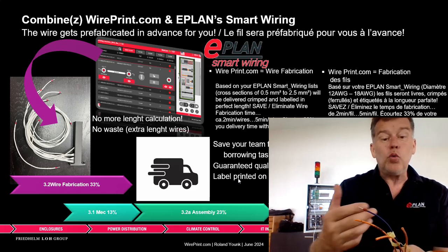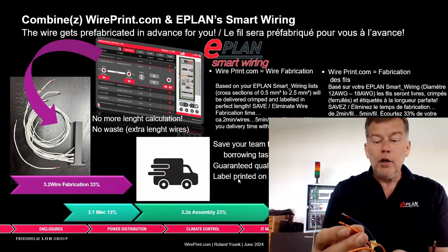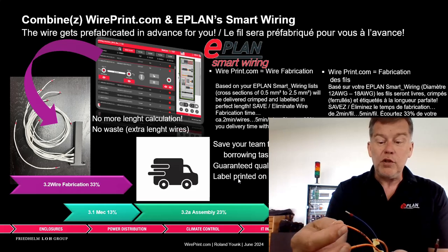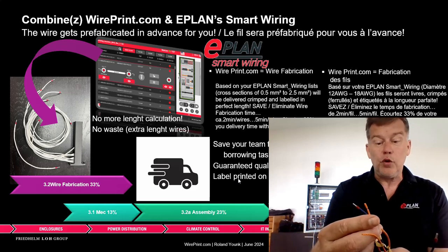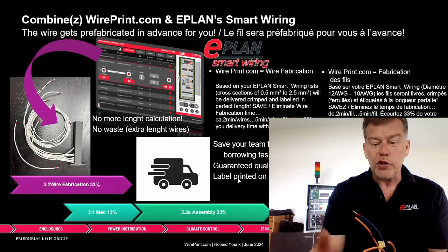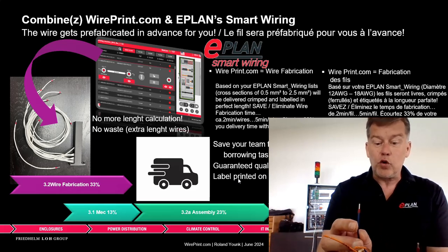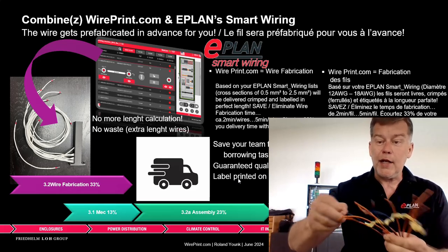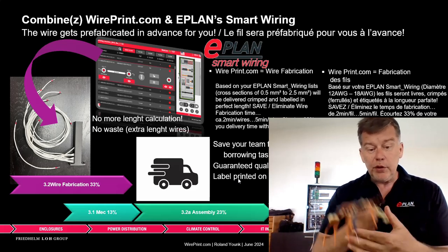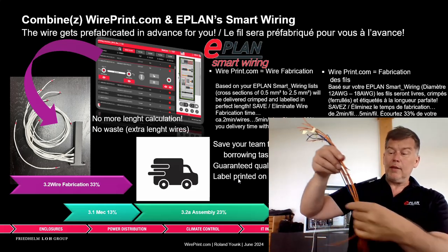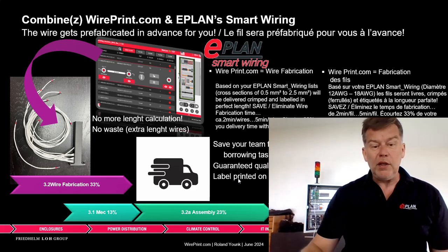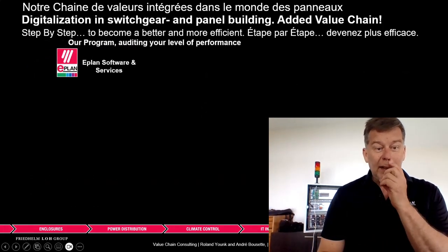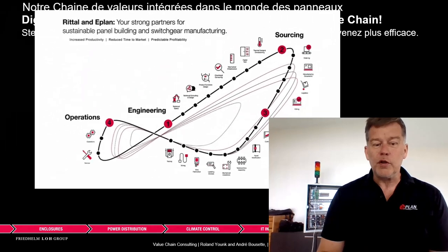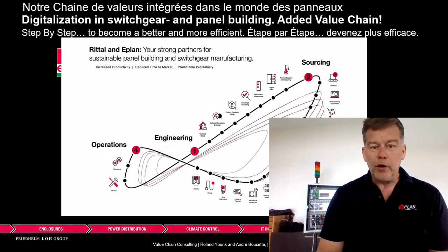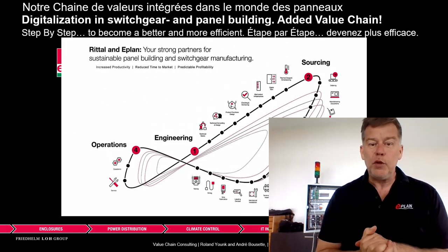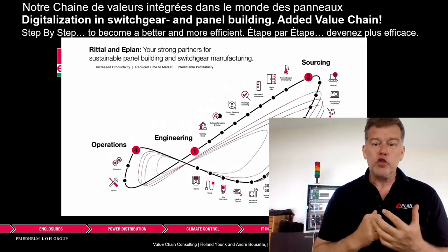Depending on what is done in EPLAN, you can ask for this wire to be just snipped off like this, so you can put your own ending, like a ring terminal or something like that, or you can have a perfect crimp. Now, this crimp is just absolutely perfect. Labeled, crimped, cut to the right length. You can see all different lengths, ready to be installed. And the idea here, in our added value chain, Rittal and EPLAN, is that we help you fabricate panels quicker.